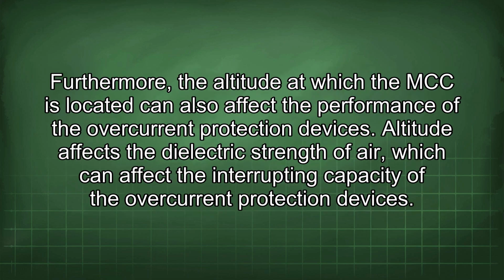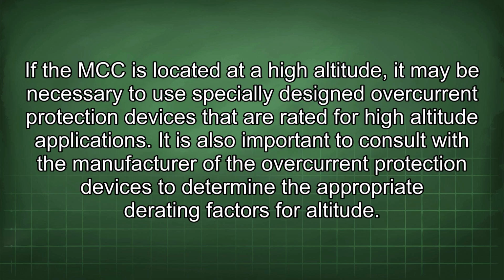Furthermore, the altitude at which the MCC is located can also affect the performance of the overcurrent protection devices. Altitude affects the dielectric strength of air, which can affect the interrupting capacity of the overcurrent protection devices. If the MCC is located at a high altitude, it may be necessary to use specially designed overcurrent protection devices that are rated for high altitude applications.